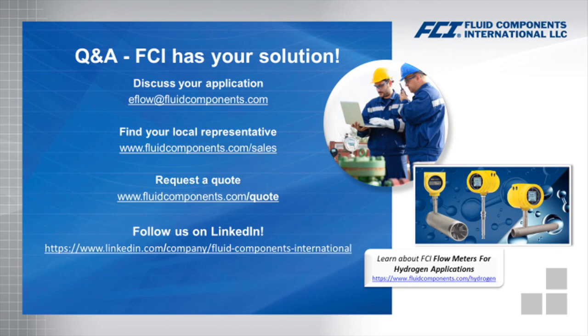How is high velocity of H2 as process fluid considered during calibration? Are the present calibration facilities H2 ready? Again, I'm not sure if we answered that one yet or not, but those type of things, velocities, pressures, temperatures, your manufacturer should be taking that into account in the calibration process. And like stated before, it's always a best practice to calibrate in actual conditions as close as possible. I can only speak for ourselves, but we do have hydrogen capable calibration here at our own facility. There are no third parties involved.